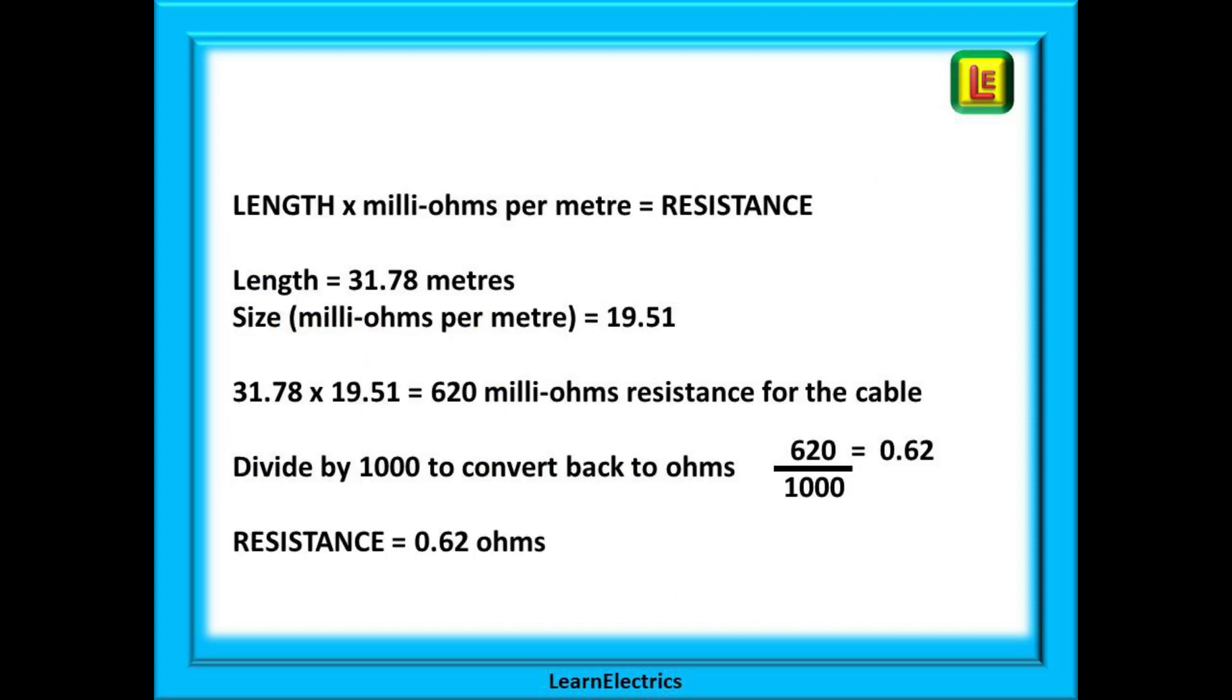So we know the length. We know how long the cable is. We want to know what the resistance or R1 plus R2 will be. Length in meters multiplied by the milli ohms from table B1 will give the resistance of the cable.